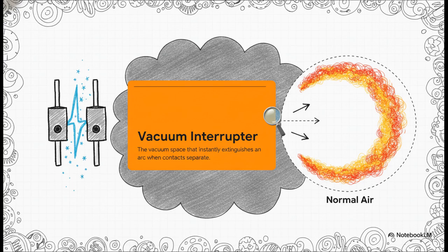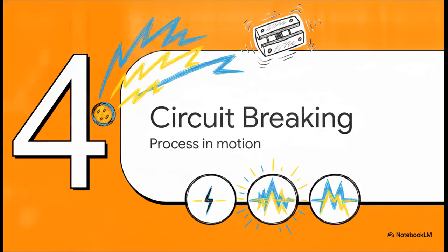But inside the vacuum interrupter chamber, there is nothing. It's exactly like the vacuum of deep space. No air, no gas, no molecules to ionize. Stripped of the medium it needs to travel through, the arc simply cannot survive, and it's starved out of existence in literal milliseconds. Which leads us to section 4, circuit breaking process.